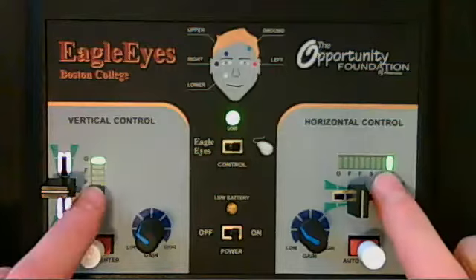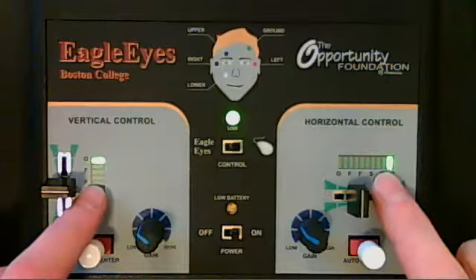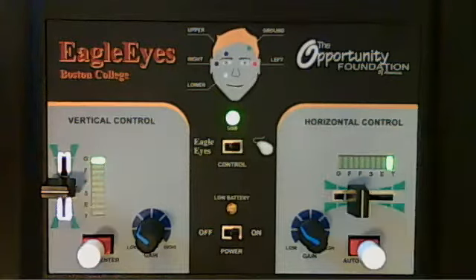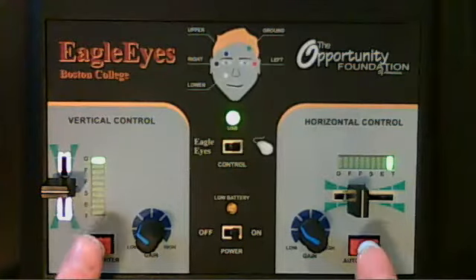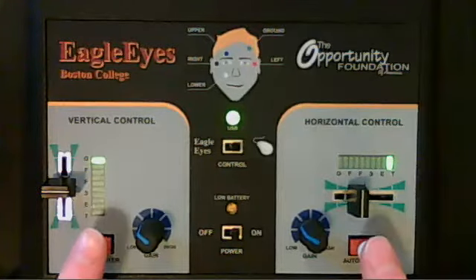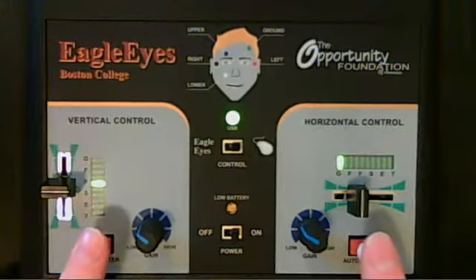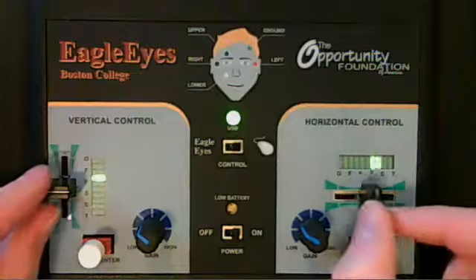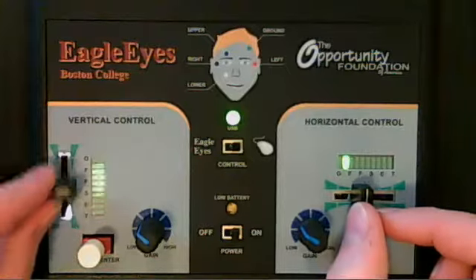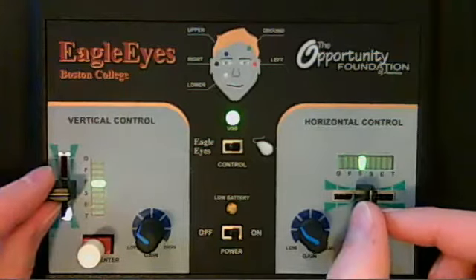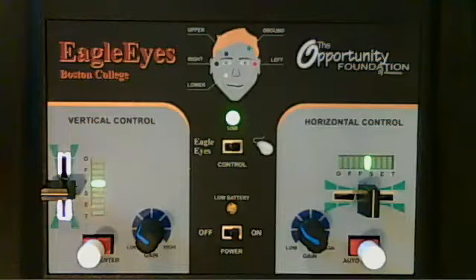Above and to the side we have the horizontal and vertical signal indicators. These will actually show the position of the signal being received as the user moves their eyes around. They also act as a power on indicator, so we know that the power is on. The two white auto center buttons return the mouse pointer to the center position. We push those two or three times successively, and once we've centered that, we should see that they now follow our offset sliders properly. And then those indicator lights will follow the user's eyes once the user's connected.